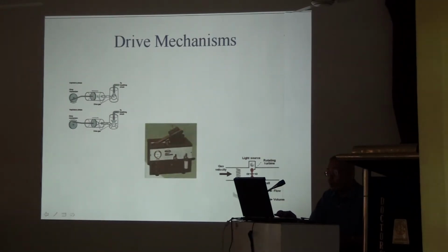Another thing, blower operated. See, there is a blower. Blower means all of you have seen a blower in your domestic appliances. That is a vacuum cleaner. Any vacuum cleaner is an analogy of a blower ventilator. It has a blower that rotates at a very high speed and draws air from one end, and at the other end the air goes out. Now, this is a continuous stream of air. If you can chop this air with an obstruction, then a seesaw movement of air will be created and that is transferred to the patient. That is a blower operated ventilator.